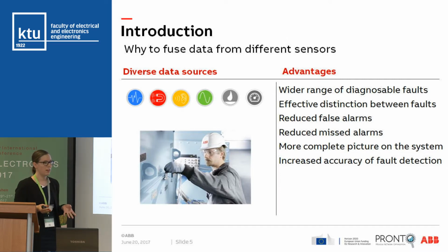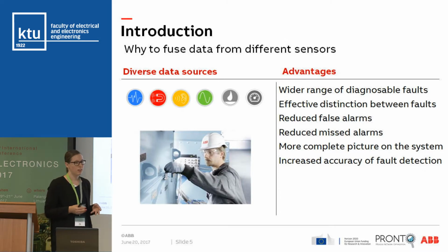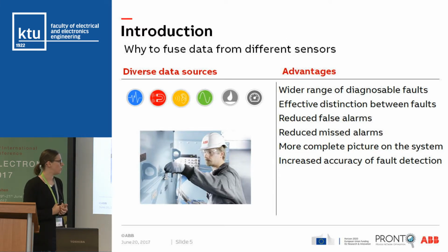False alarms occur when the system or equipment is actually healthy, but the algorithm or condition monitoring system thinks there is a fault, so maintenance personnel come and find there's no fault, and they had to stop production - that's also a problem. In missed alarms, the situation is the opposite: the system is reported healthy, but there is actually a fault, and because of that fault there might be a stoppage in the production or system.